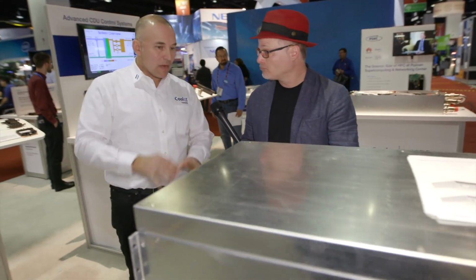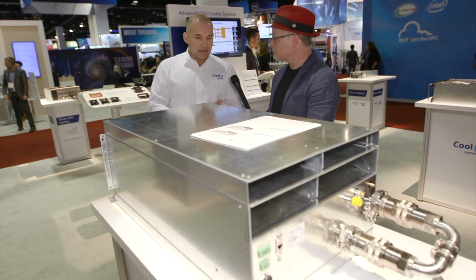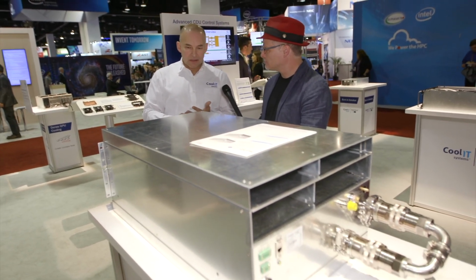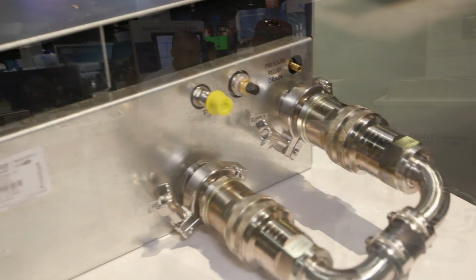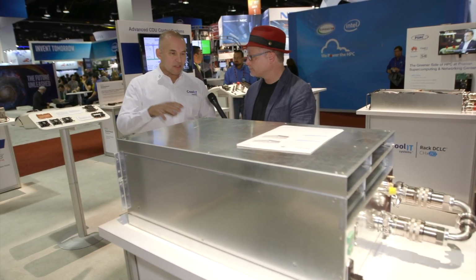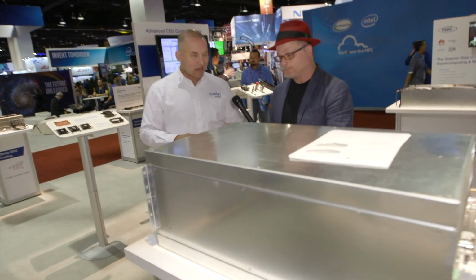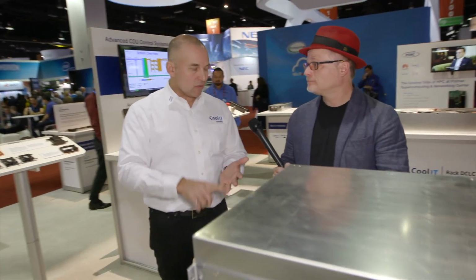So inside this box is a liquid-to-air heat exchanger, N+1 redundant pumping, a full instrumentation so that you can tell exactly what the water temperature, pressure, flow, all being reported through our standard control system. Is that accessible over the network so an admin could see what was going on cooling-wise? Absolutely. Wow. Yeah, in fact, let's have a look at that.